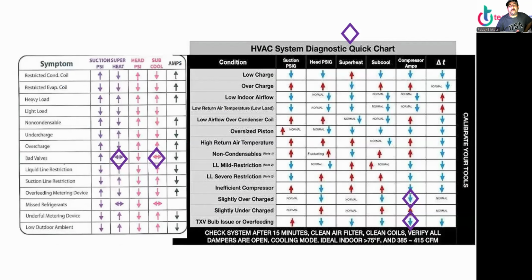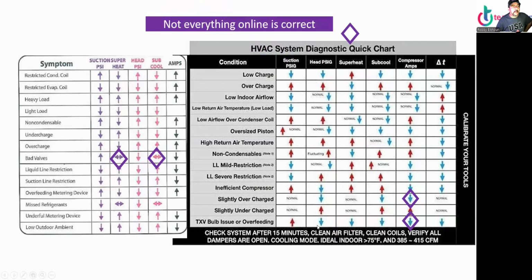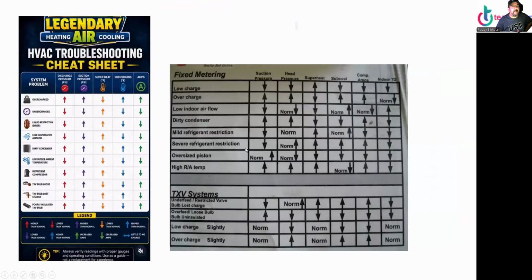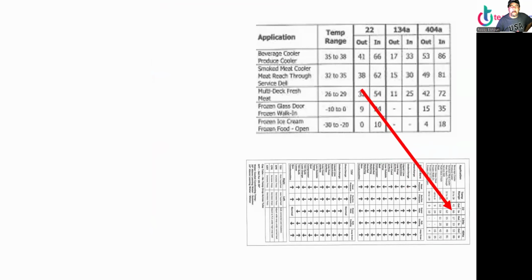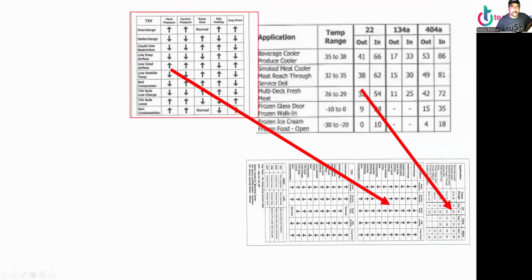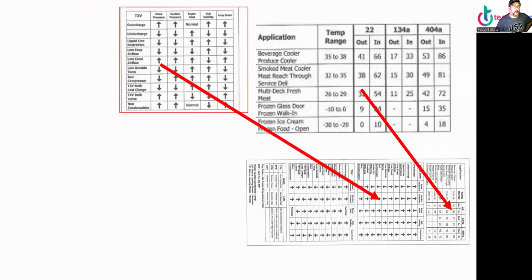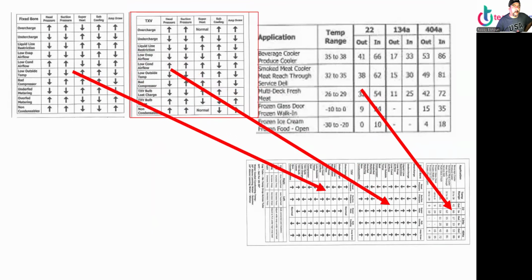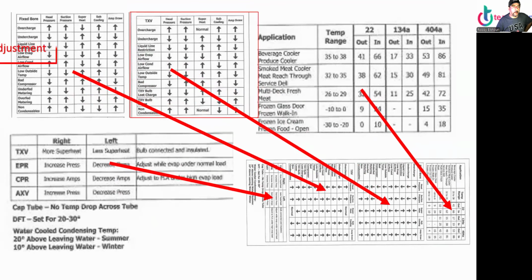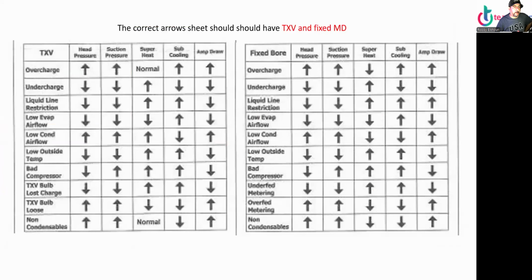Alrighty, so not everything's correct online, because you can see those things don't match up. Not everything's correct online, but I found one that is correct. And this is split in 4 places: 1, 2, 3, and 4. And this is how to make adjustments: TXV, EPR, CPR, and automatic expansion valve.